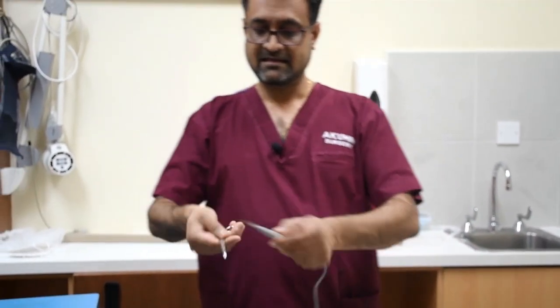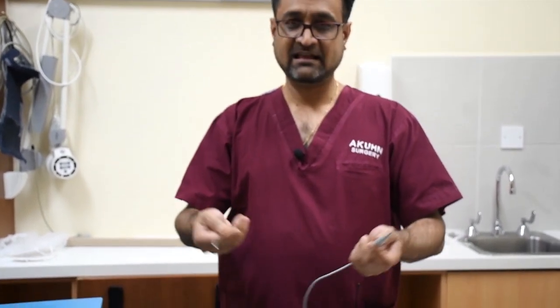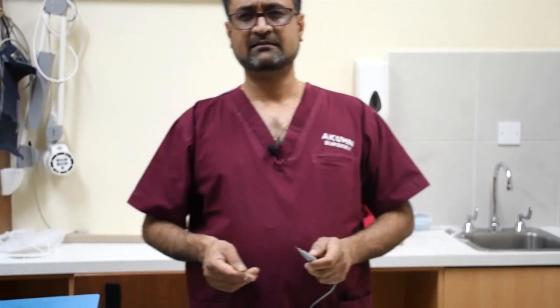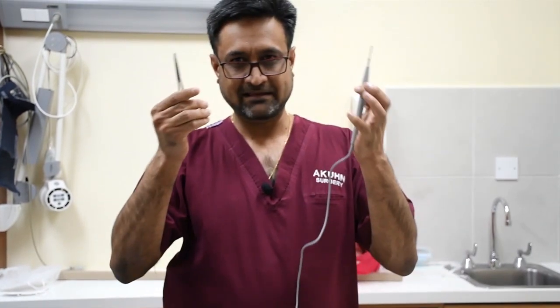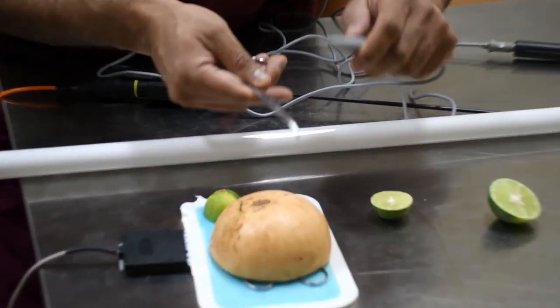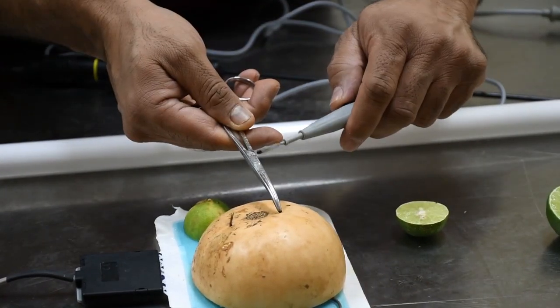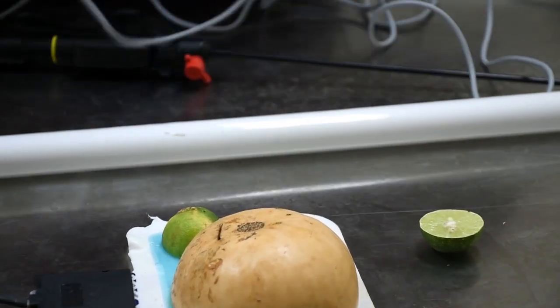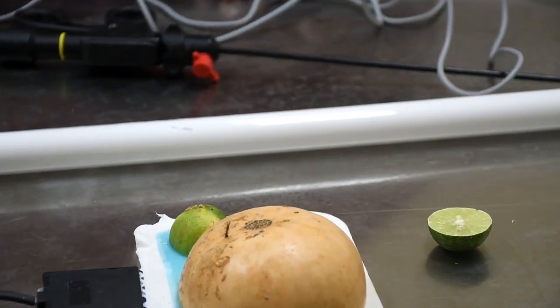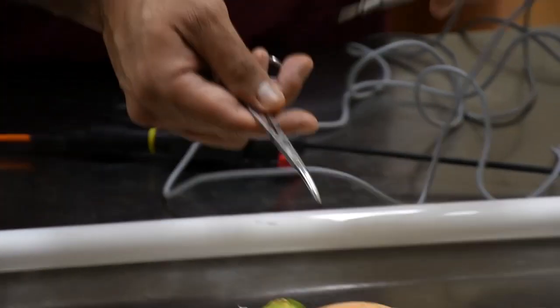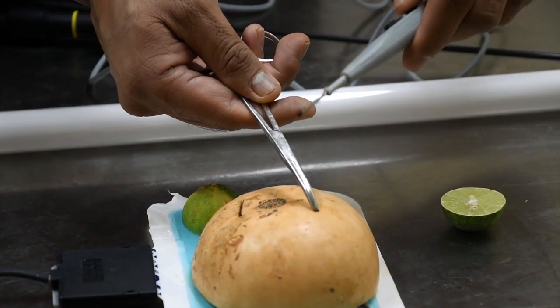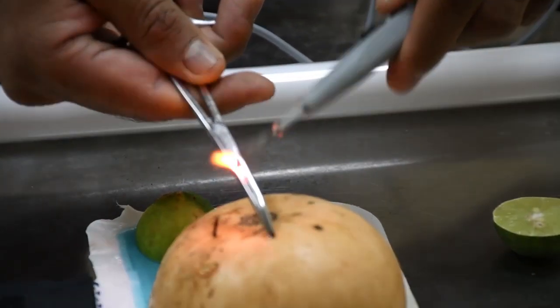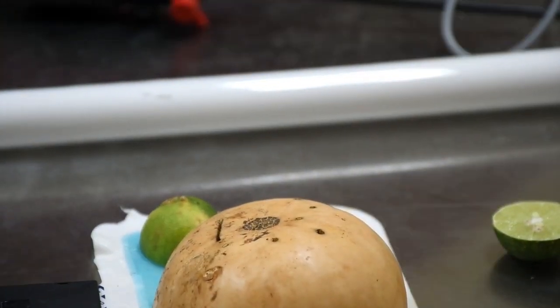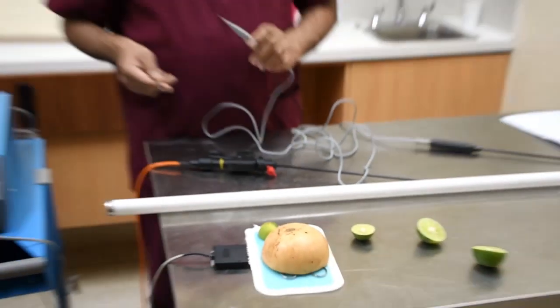Now we'll have to discuss why that is happening. I'm not insulated, I'm not wearing gloves, and it's a very high frequency, but I am not getting burnt. Now when I activate it on this, you can see that it is activating. So I activate it, and there it's activating and burning the patient where we want. The same thing happens when I use the blue, the coag, it still does the same thing. The difference is one is very high voltage, one is low voltage.